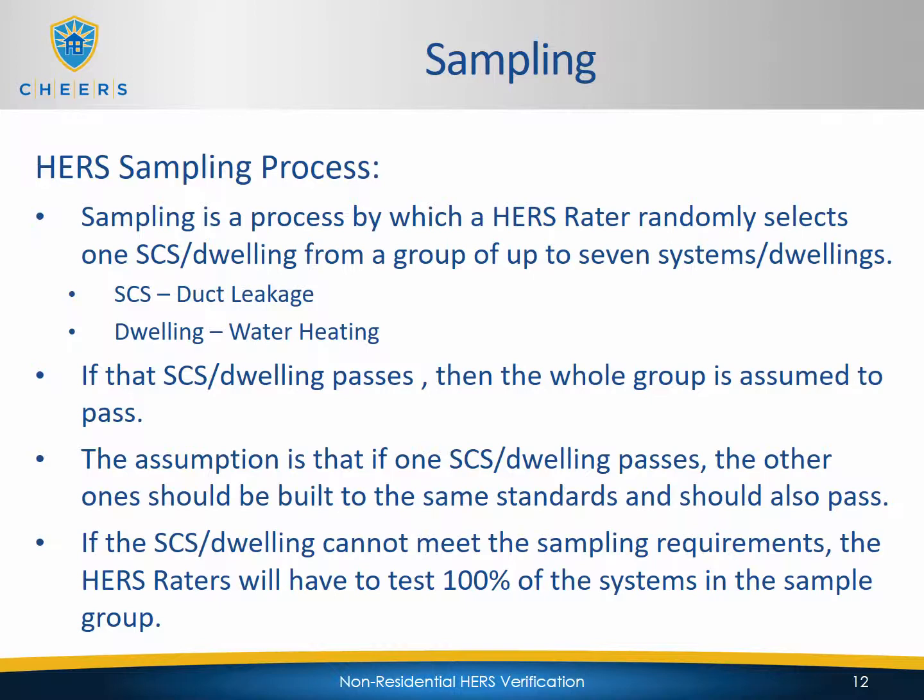The sampling process is similar to the residential side. Sampling is a process by which a HERS rater randomly selects one space conditioning system or dwelling from a group of up to seven systems or dwellings — SCS for duct leakage, dwelling for water heating. If that system or dwelling passes, the whole group is assumed to pass. If the selected SCS or dwelling cannot meet the sampling requirements, the HERS rater will have to test 100% of the systems in that sample group.